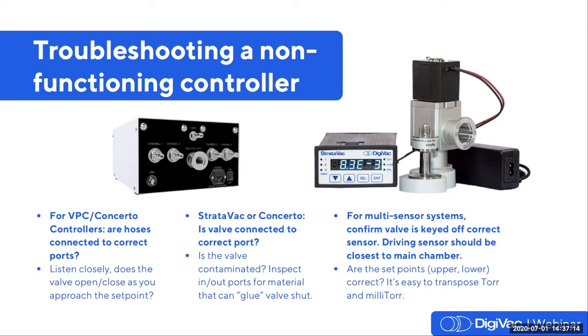For multi-sensor controllers, the valve is only keyed to 1 sensor and will activate at the set point as read by that sensor. So ensure that the driving sensor is the closest to the main chamber, because that is the level that you're attempting to read in the main chamber. It stands to reason that the sensor is as close to that chamber as possible. Also ensure that you've entered your set points correctly. Sometimes folks will transpose torr and millitorr, not realizing that 1 millitorr is in fact 1/1000th of 1 torr. So 1 torr corresponds to 1000 millitorr.